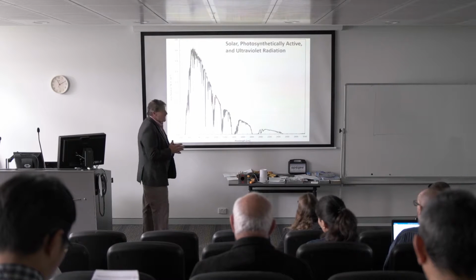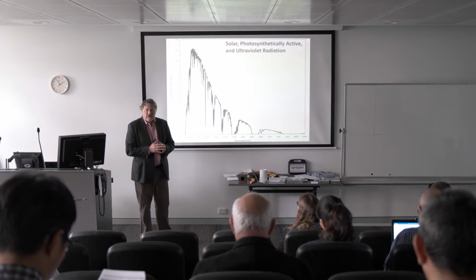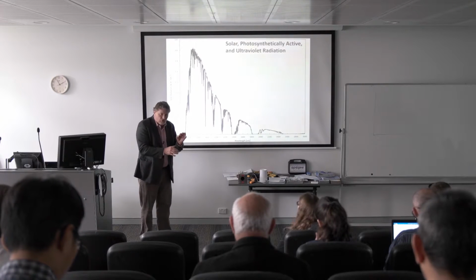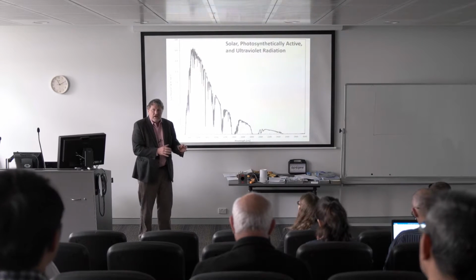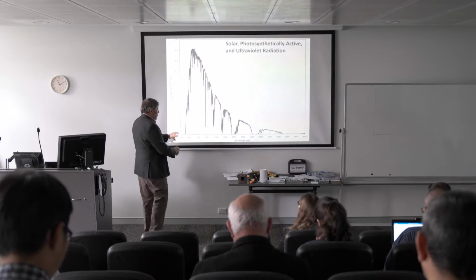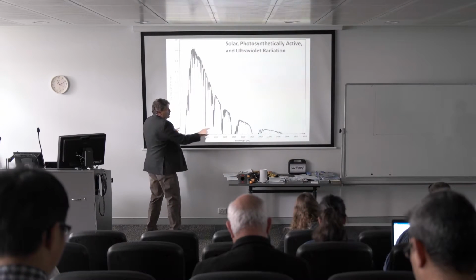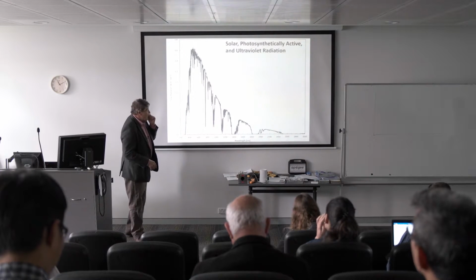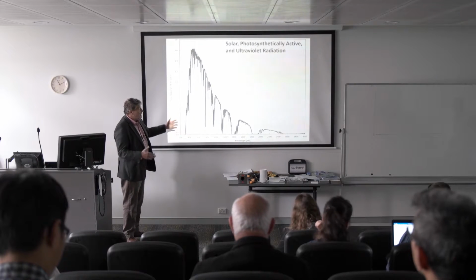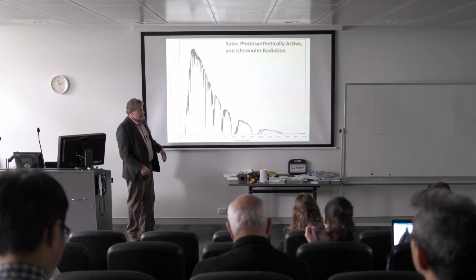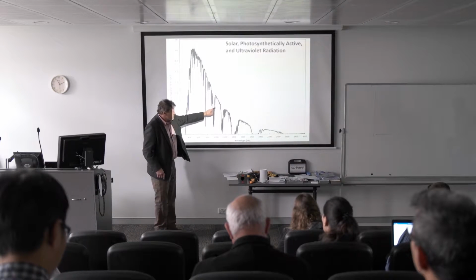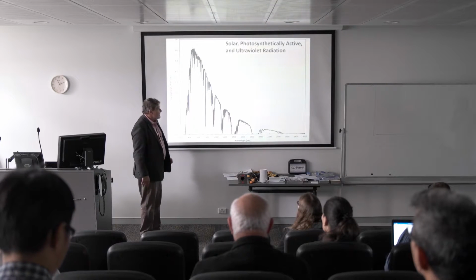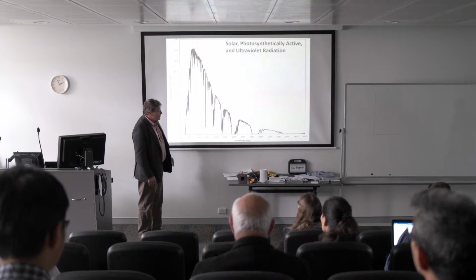This comes from the fact that black body pyranometers, and you look at them and there's a glass dome and a black disc, record all of the radiation over this whole solar spectrum. This is the entire solar spectrum on a typical sunny day. They measure all of this. These are all giant bands of absorption of water vapor in the spectrum. Outside the atmosphere, it's a smooth curve.